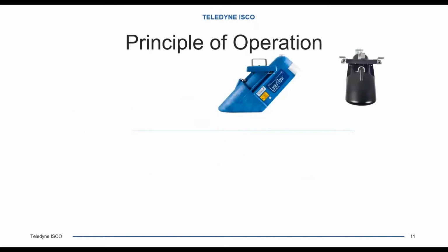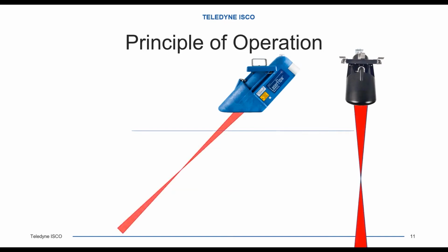All right, so let's give you a little different look here. This is a side view and a front view. Again, both are doing the same thing. We're measuring the distance to the water. Once we know where the water is, we focus that laser. I like this picture because it gives you a better idea when you're out in the field installing one of these. If you put your hand underneath the laser, you'll see a dot the size of a quarter roughly.